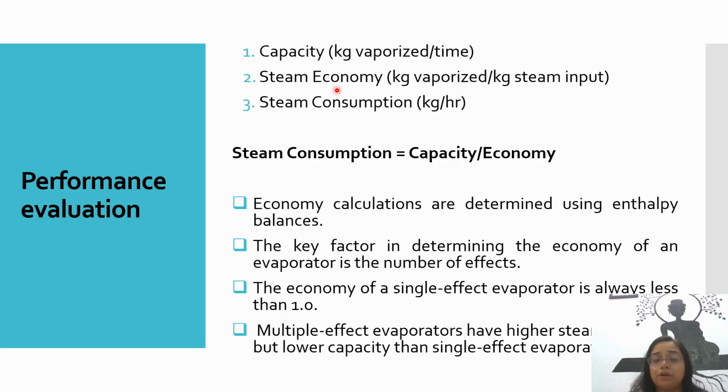performance of any evaporator. So what we have seen is that for a single effect evaporator, the steam economy is always less than 1. Clear? So it will never be 1, or greater than 1, in case of a single effect evaporator. However, we will see later on that in case of a multiple effect evaporator, the steam economy will be greater than 1, that we will see in the coming slides.